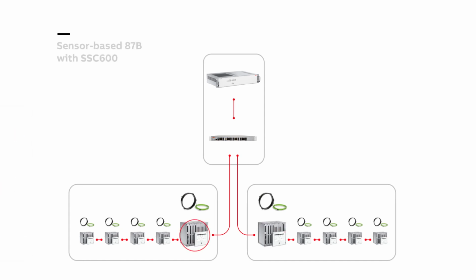On the other hand, with sensor-based 87B, you only need the protection relay for the protection functions inside the panel and a set of sensors, current, voltage, or combi sensors. The panels are identical for bus A and bus B, and there is no need to have additional hardware or devices. You only need to distribute the sampled measured values from the protection relay via the Ethernet switch to SSC600. In this case, you can combine the disturbance recorder with 87B and another application in one device.